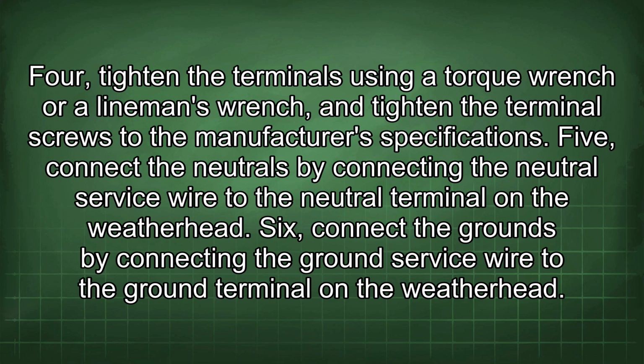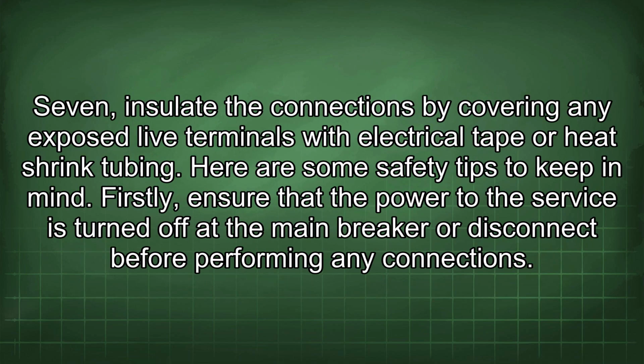specifications. 5. Connect the neutrals by connecting the neutral service wire to the neutral terminal on the Weatherhead. 6. Connect the grounds by connecting the ground service wire to the ground terminal on the Weatherhead. 7. Insulate the connections by covering any exposed live terminals with electrical tape or heat shrink tubing. Here are some safety tips to keep in mind.